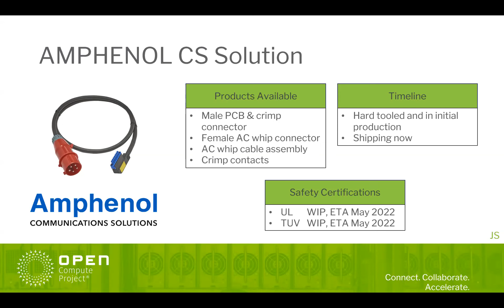One topic we discussed is disconnect under load. For this requirement, we initially stated in the specification that the connector must survive 50 cycles of insertion and removal at 150% of the maximum rated current and voltage. This language was taken from the rack PDU specification, the IEC specification under input mains, again just to protect the equipment and ensure there's no degradation of the contacts in adverse disconnection environments.